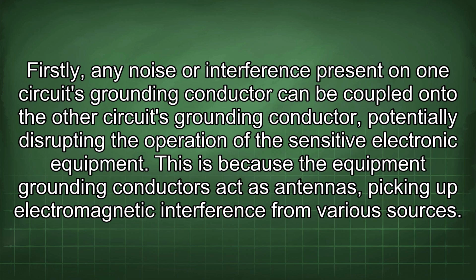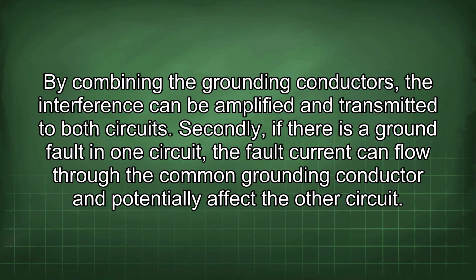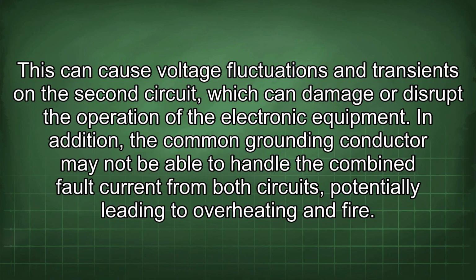This is because the equipment grounding conductors act as antennas, picking up electromagnetic interference from various sources. By combining the grounding conductors, the interference can be amplified and transmitted to both circuits. Secondly, if there is a ground fault in one circuit, the fault current can flow through the common grounding conductor and potentially affect the other circuit. This can cause voltage fluctuations and transients on the second circuit, which can damage or disrupt the operation of the electronic equipment. In addition, the common grounding conductor may not be able to handle the combined fault current from both circuits, potentially leading to overheating and fire.